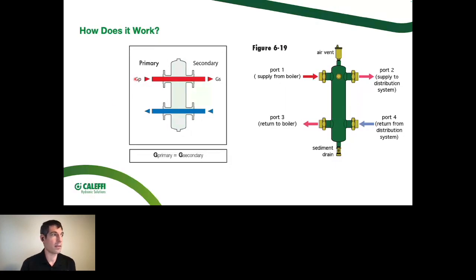So in that case, if you had 10 GPM on the boiler side and you had 10 GPM on the system side, you could have just a straight shot across the hydro separator and back. So in this, I see in the chat that the one zone example is right. In this example, I could put a little drop of food coloring right here, and it would just kind of float right there. It wouldn't go anywhere because we've just got kind of stagnant conditions right in the center as we're going straight across the top and straight across the bottom. So it would look like this. We've got two wheels spinning at the exact same speed.